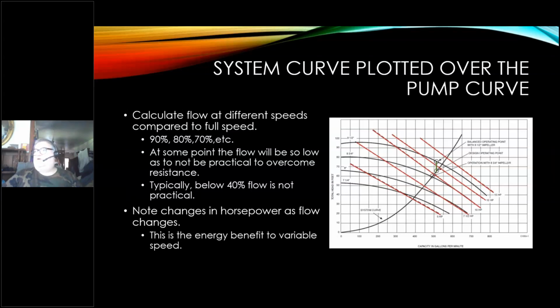Changes in horsepower as the flow changes. This is the energy benefit. This is how we get the benefits of variable speed, is that the horsepower drops significantly. But there is some discussion about exactly how to calculate that. Again, here's our operating point at the highest point. It's actually above the system curve, so this may be the large pump that we chose.